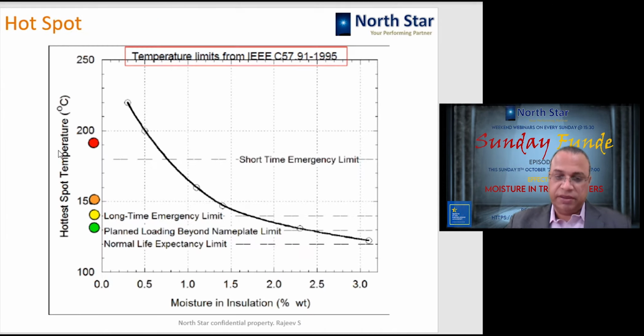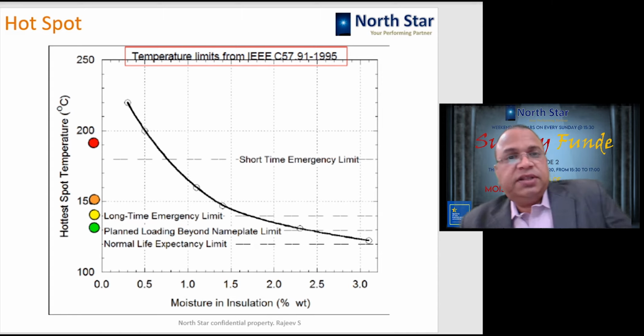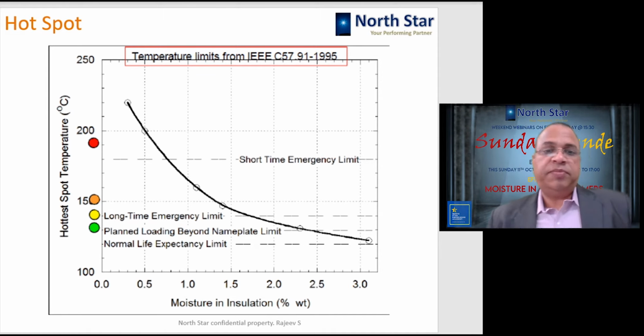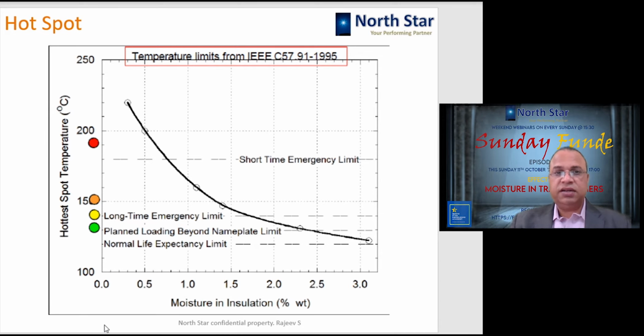So how does moisture affect the loading capability? We know hotspot is the maximum hottest temperature in the transformer, and this hotspot depends upon the moisture in the transformer. Here it is, this chart is from IEEE C57.91, which is talking about the percentage moisture in solid insulation, by weight, and this is the hotspot temperature. Here you can see when the moisture is low, when the transformer is dry, the hotspot temperature can be around 200 degrees centigrade. Of course, it is short time emergency loading.